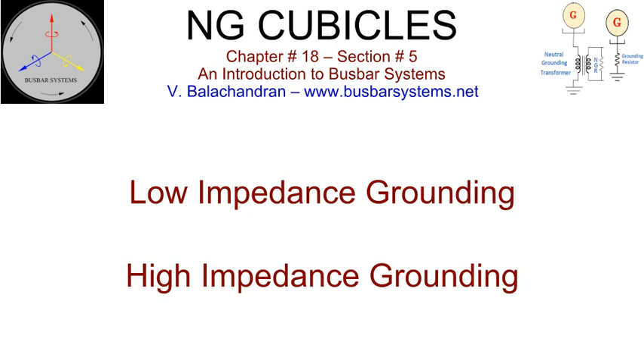a neutral grounding transformer. Compensated grounding, also known as reactor grounding or resonant grounding, falls under the category of high impedance grounding, where instead of a resistor, a reactor is connected to the secondary of the transformer. A perfectly tuned reactor will effectively suppress the ground arc, and consequently it is also referred to as arc suppression coil. Compensated grounding is more expensive and requires tuning.